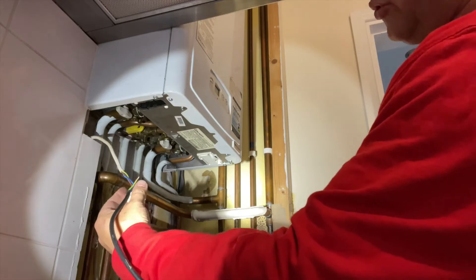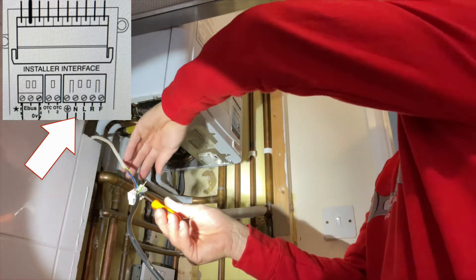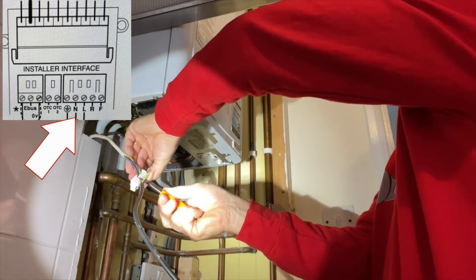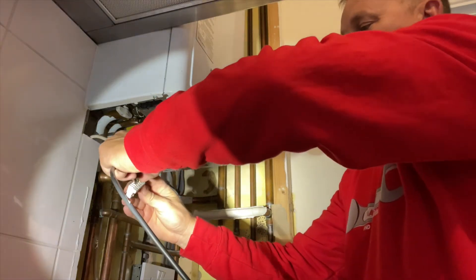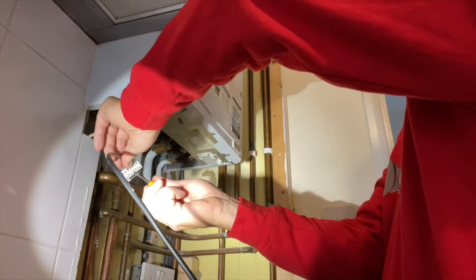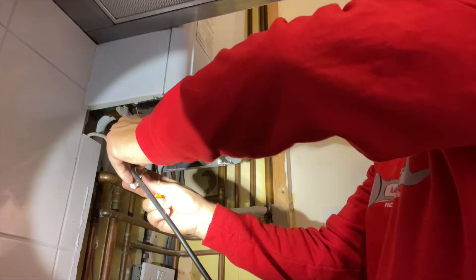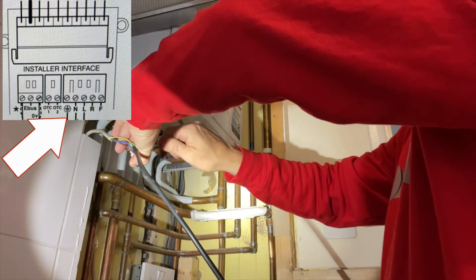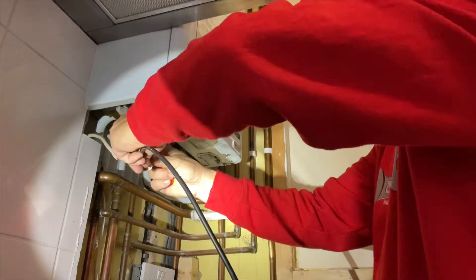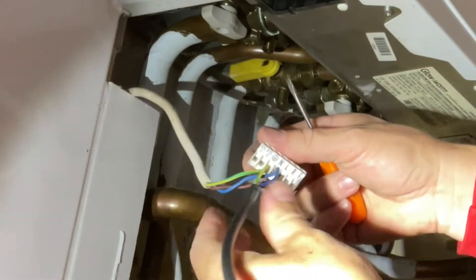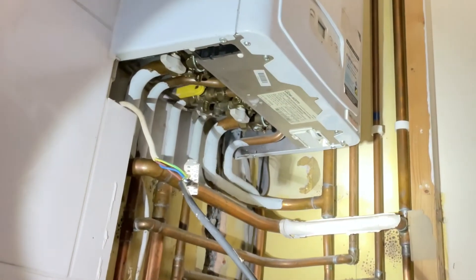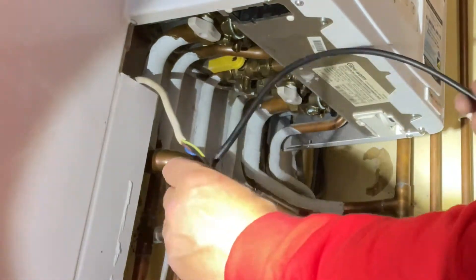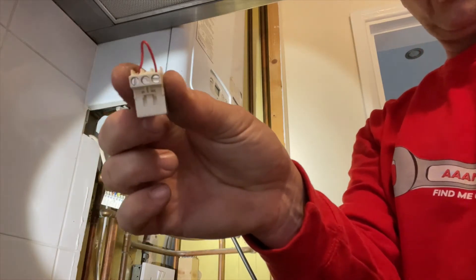We'll do the same with the neutral. Pop that blue one into there and tighten that one up. And then the earth is the same again. We'll just crack that one off and slide that earth in. And then we'll do the earth bump as well. That's those three in there. If you can spur off of the boiler feed like that, you won't need to put a fuse link in at all. That's a perfectly good way to wire this up. And then last but not least is our little jumper wire there.